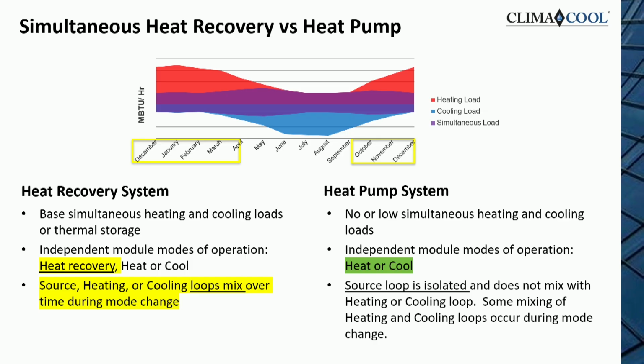So just kind of the key takeaways from, what are we chasing? We're really chasing that purple band. The more purple there, the more efficient the system is, the more we're operating in simultaneous heating and cooling. And then just to distinguish what's a heat pump system, it's where you're going to have just a dedicated heating mode, dedicated cooling. They're not overlapping that much.